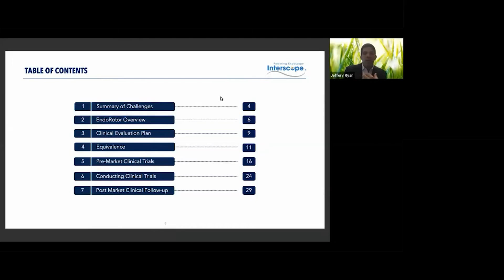With respect to MDR, the risk classifications have really changed. A lot of class 1 requirements now need a technical file. That didn't need to be there before. It needs its own clinical evaluation report. Also didn't need to be there. And class 1 is only the cusp, because once you get into 2A and 2B, as well as class 3 devices, the requirements continue to get stricter for the rules of equivalence that you want to adopt.